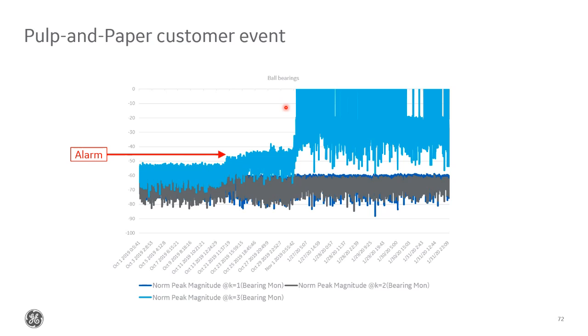Another event that one of our colleagues presented at an IEEE pulp and paper event was a customer who had ESA. They separately graphed all these values like you show here in a separate piece of software. But what happened was they were in normal operating mode. The 869 operated an ESA alarm here for bearing faults. The customer did not look at the alarm values. They just let it run, didn't notice anything was wrong. So the 869 continued to gather data, and we can see that the fault values are continuously getting worse and worse and worse until a catastrophic failure.